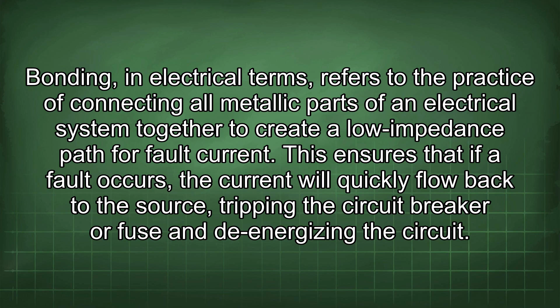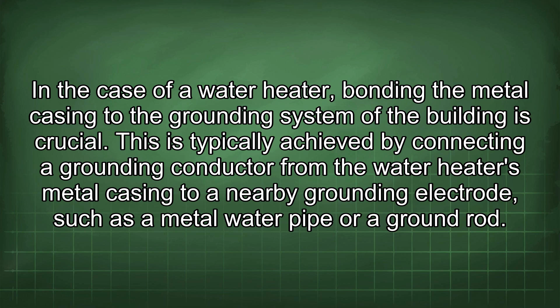This ensures that if a fault occurs, the current will quickly flow back to the source, tripping the circuit breaker or fuse and de-energizing the circuit. In the case of a water heater, bonding the metal casing to the grounding system of the building is crucial. This is typically achieved by connecting a grounding conductor from the water heater's metal casing to a nearby grounding electrode, such as a metal water pipe or a ground rod.